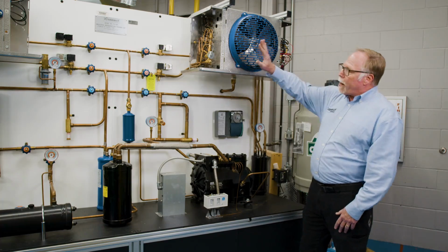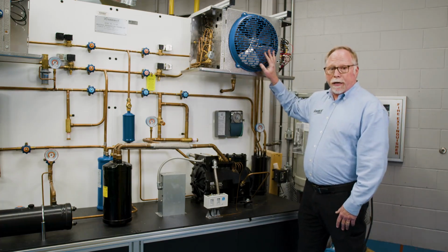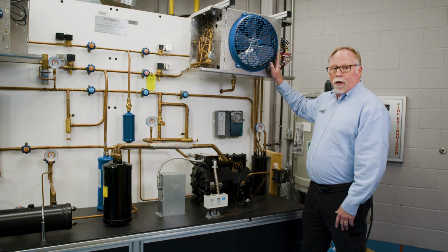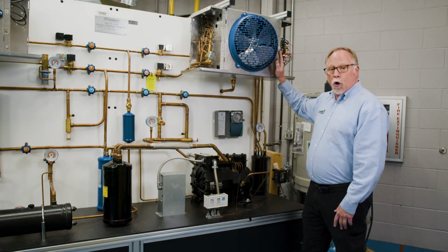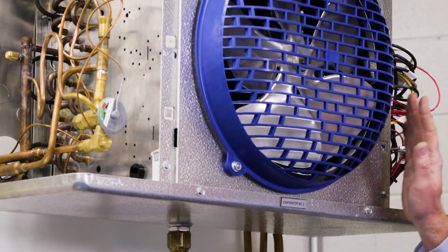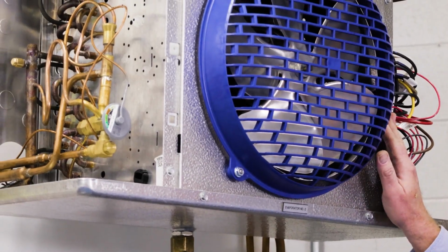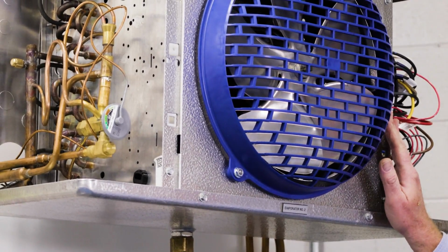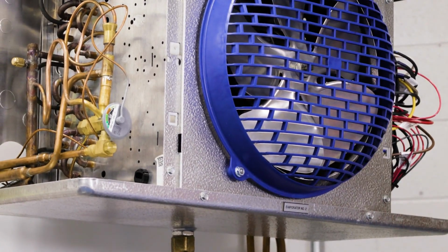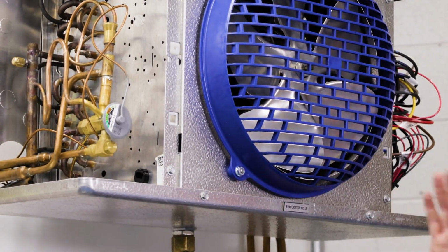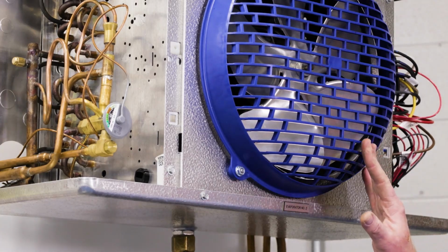Each evaporator coil has its own electric circuit. On the freezer side, we have electric heaters, which you can teach them how to check voltage to, and how to ohm out those heaters. We have the DFT control, and also the hot gas bypass. Here we've got a full electrical side that you can teach, either broken into multiple modules or taught in one overview.